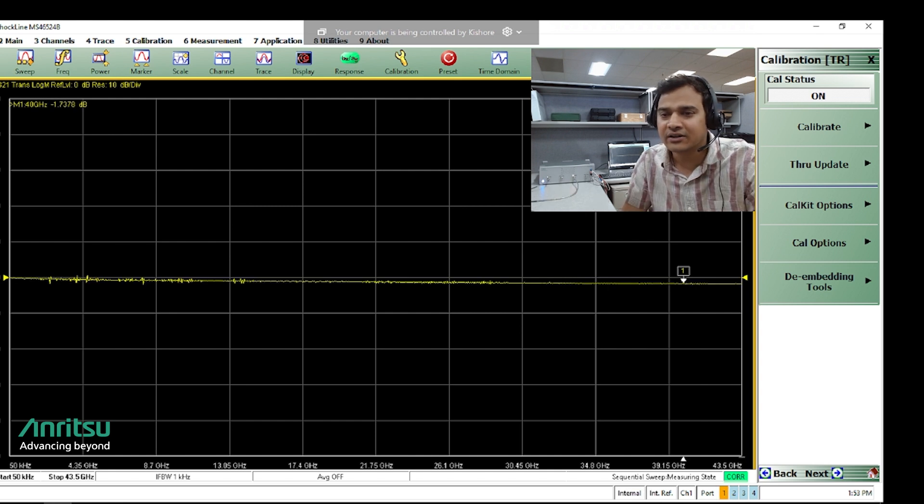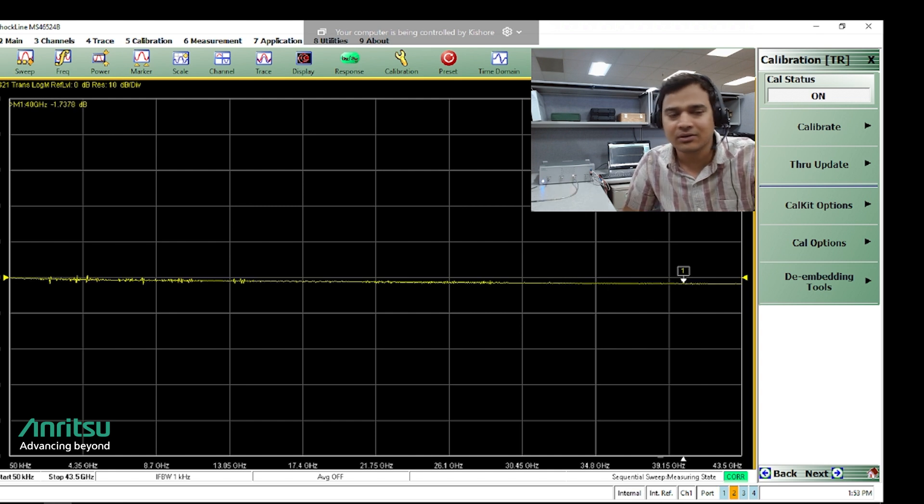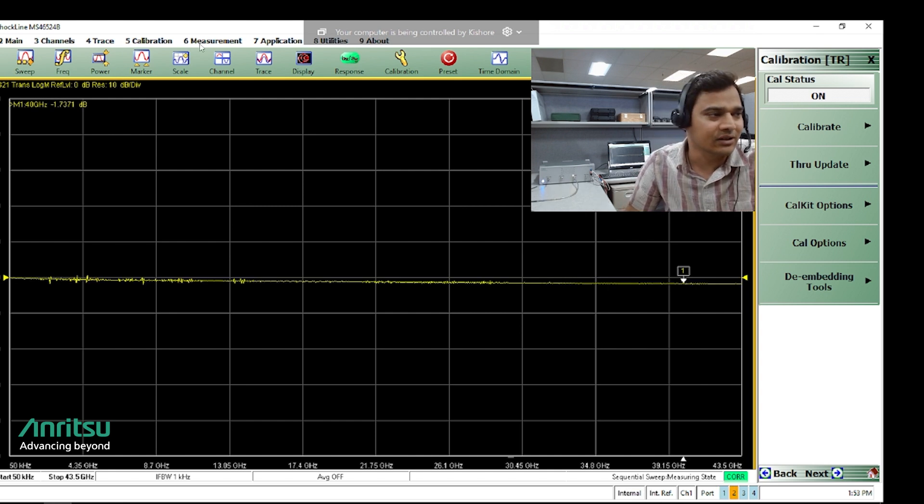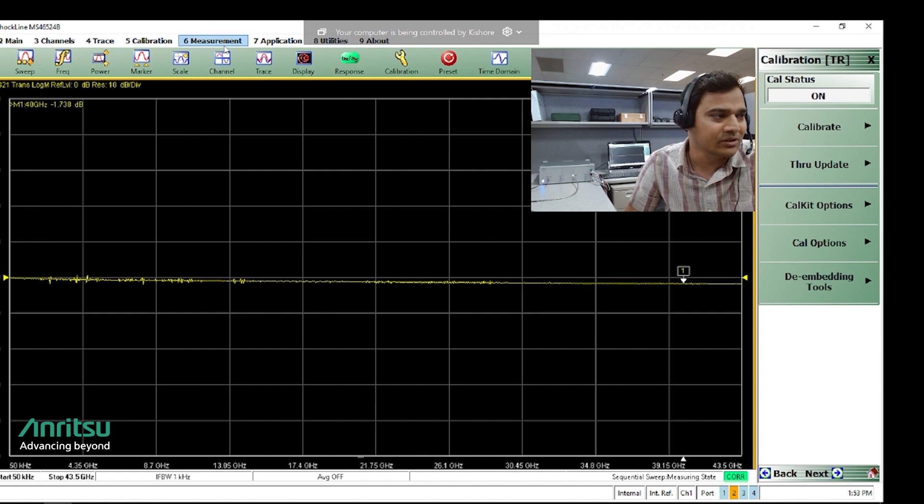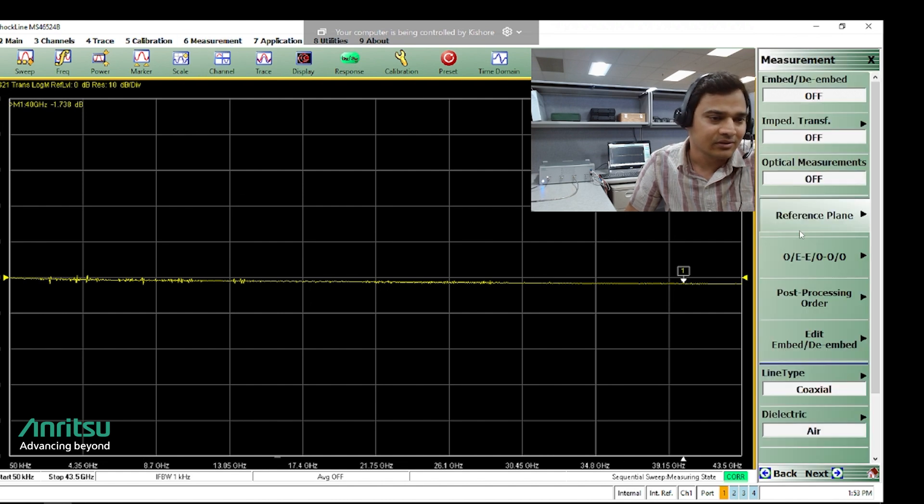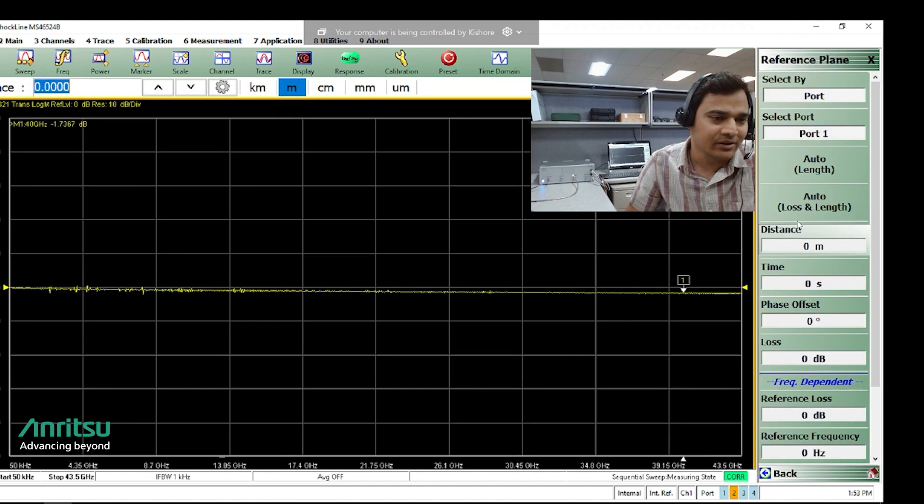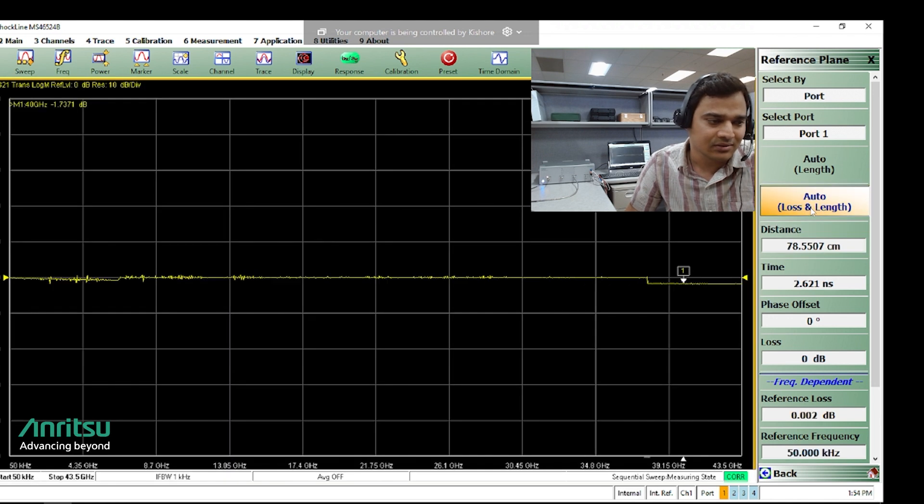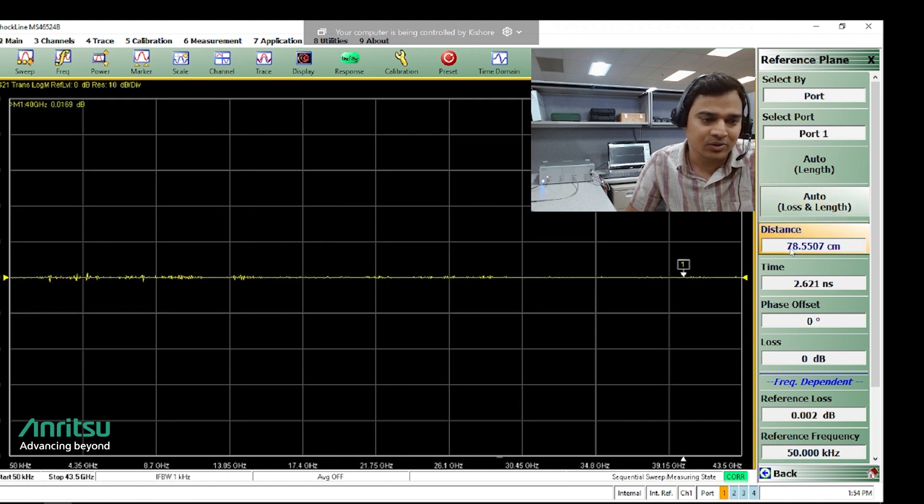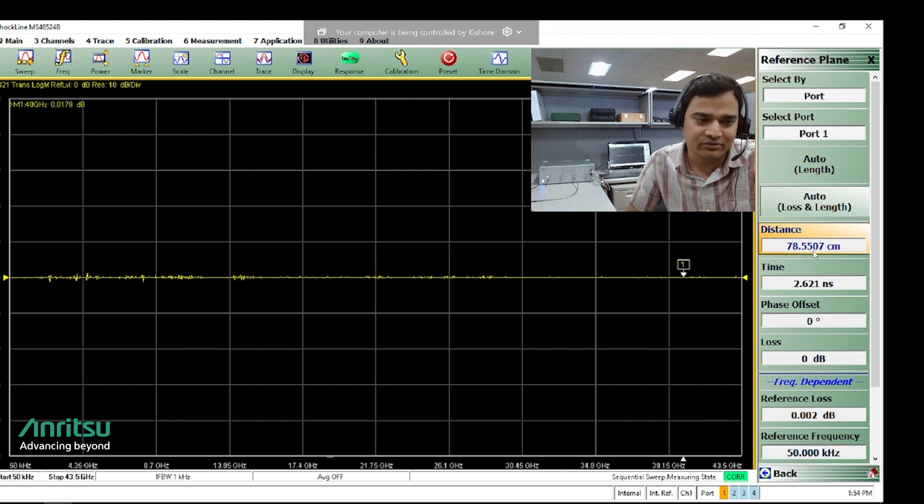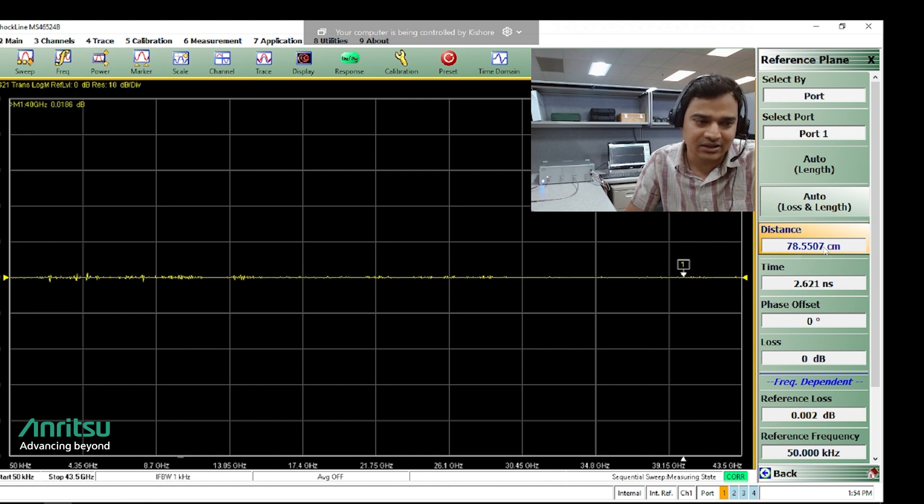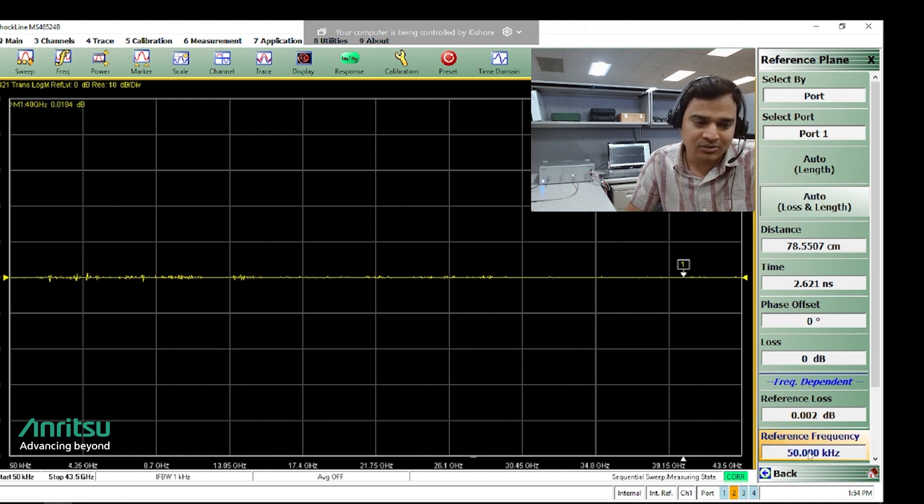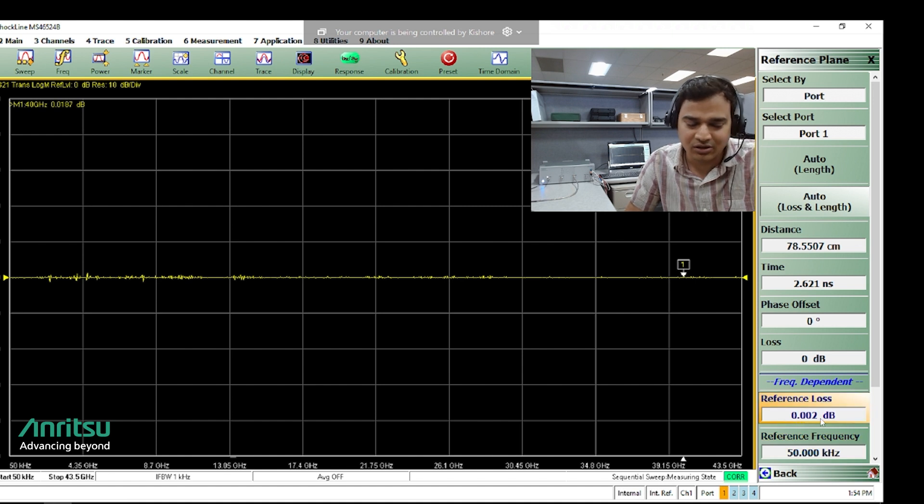I have connected the DUT cable. Now to measure the electrical and loss parameters we will go to measurement reference plane, click on auto loss and length. This gives the distance. What we see here, 78.55 centimeters, is the electrical length of the cable. And the loss profile at reference frequency of 50 kilohertz has 0.002 dB loss.